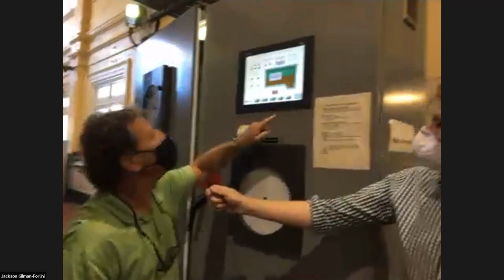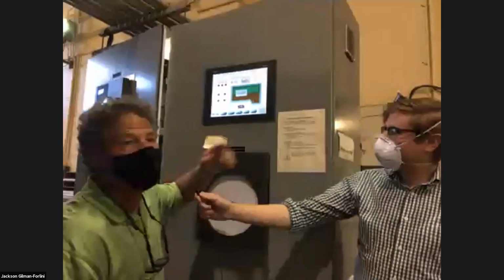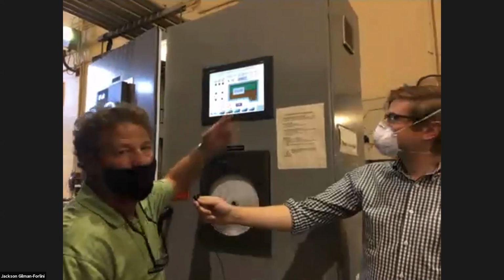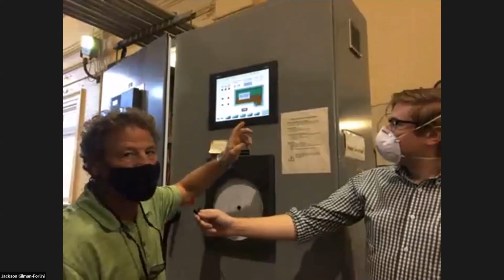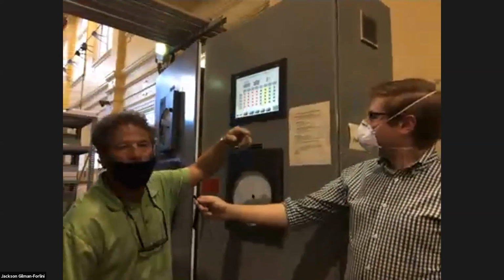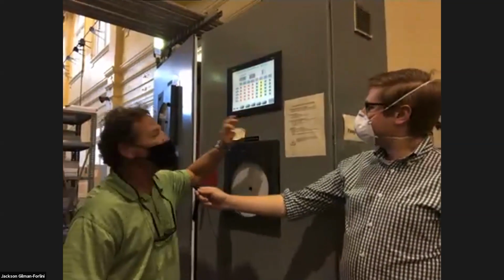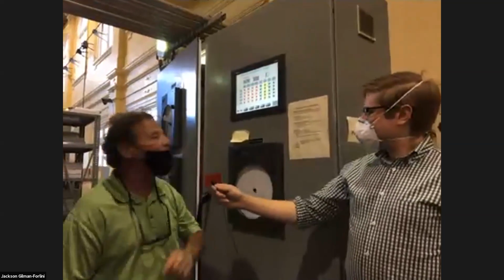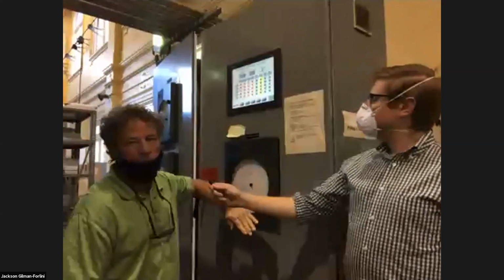This is currently the HMI, which is Human Interface Module, and it allows the operator to see what is going on at the present time. And this computer will actually select which pump the operator desires to run, and it runs through preset set points at water levels in our wet well. So it is set to come on at a certain level and shut off at a certain level.